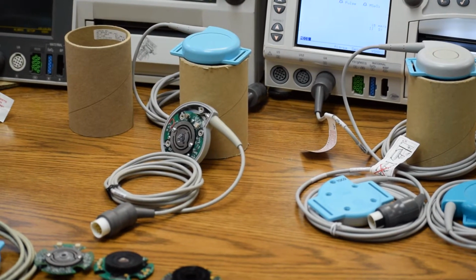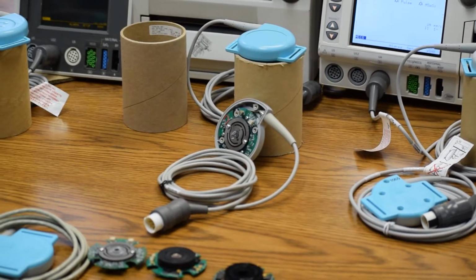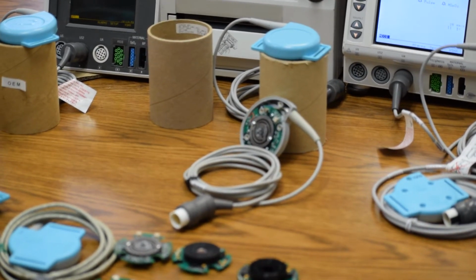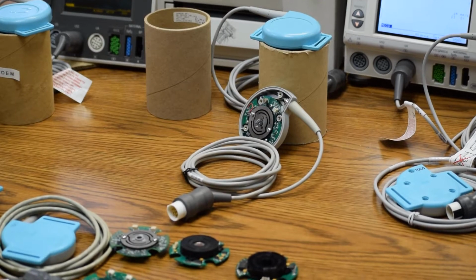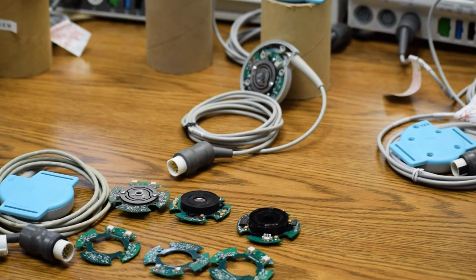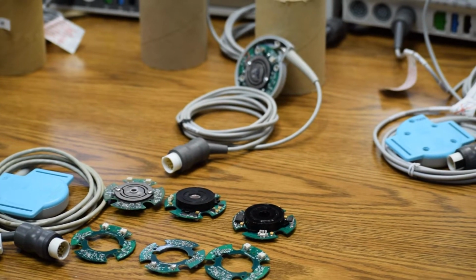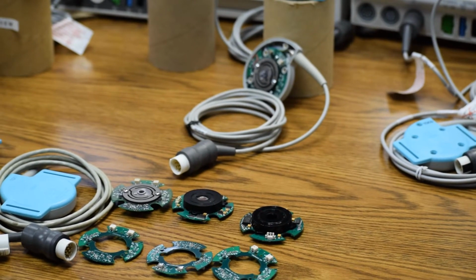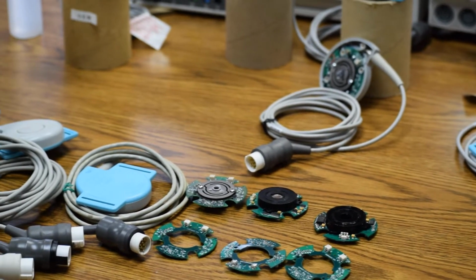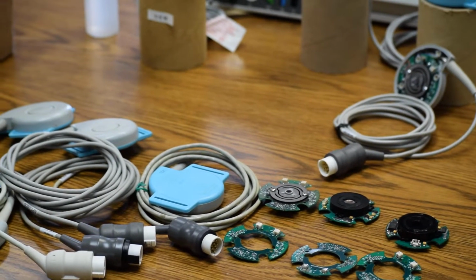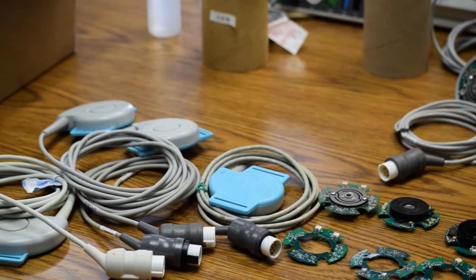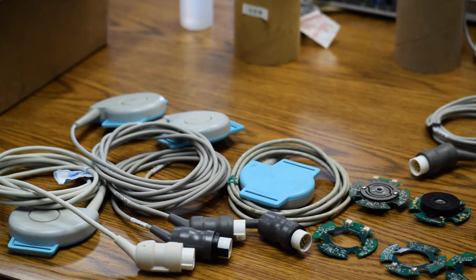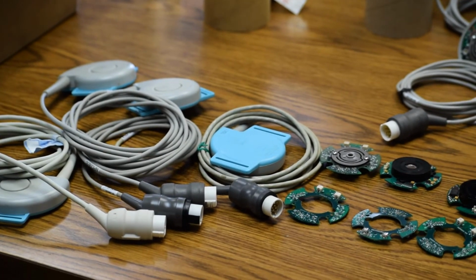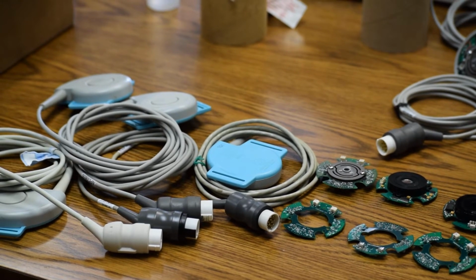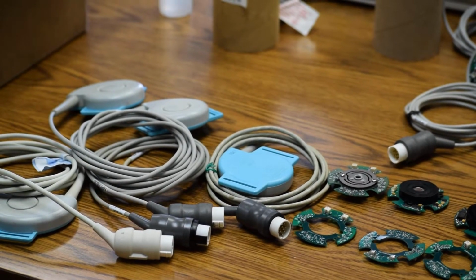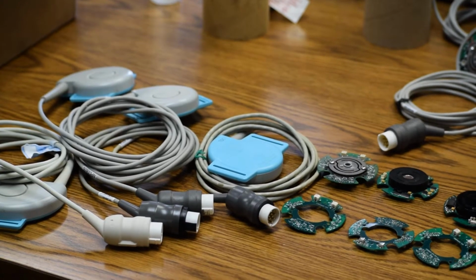No doubt, there is a significantly low cost of repairs in the range of $85 down to $40, depending on the service company and what aftermarket parts they use. With all non-GE parts, the trade-off is repeated failures, which amount to spending more money in a short span of time as compared to OEM quality repairs or replacement with brand new GE units in the first place.